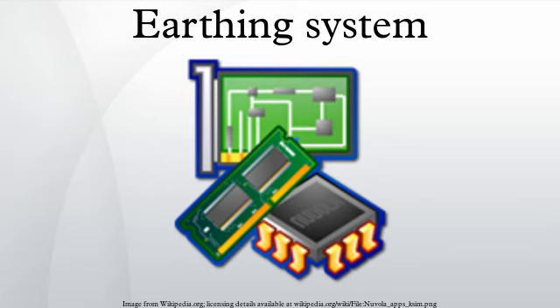In the pre-RCD era, the TT earthing system was unattractive for general use because of its worse capability of accepting high currents in case of a live-to-PE short circuit. But as residual current devices mitigate this disadvantage, the TT earthing system becomes attractive for premises where all AC power circuits are RCD protected. The TT earthing system is used throughout Japan, with RCD units in most industrial settings. This can impose added requirements on variable frequency drives and switched mode power supplies, which often have substantial filters passing high frequency noise to the ground conductor.